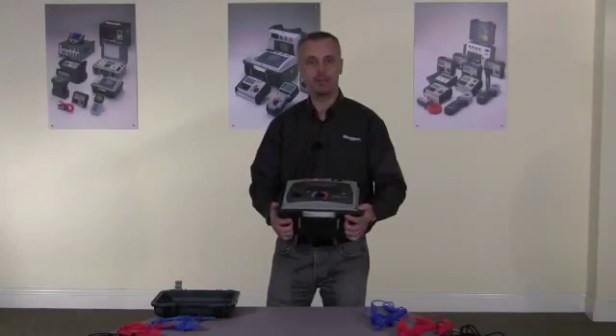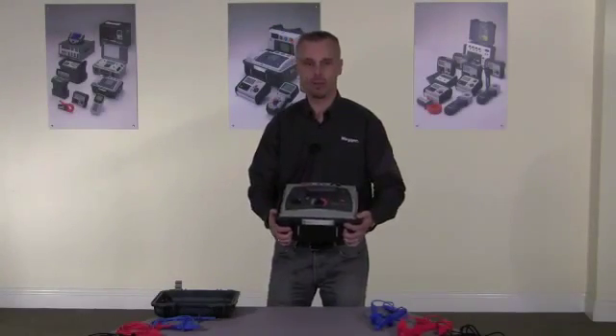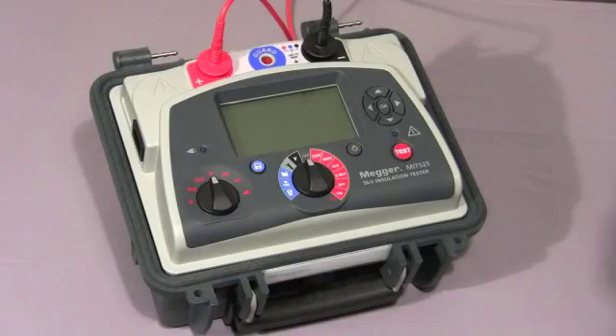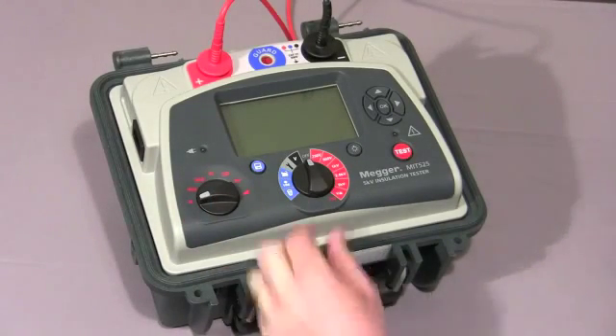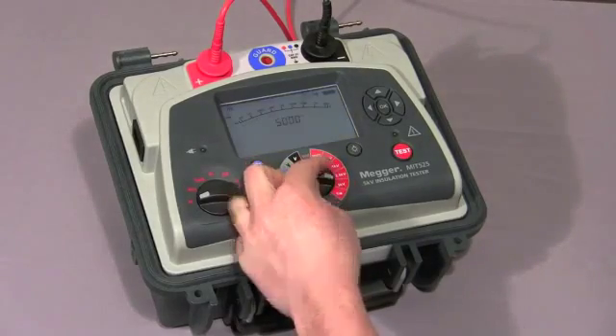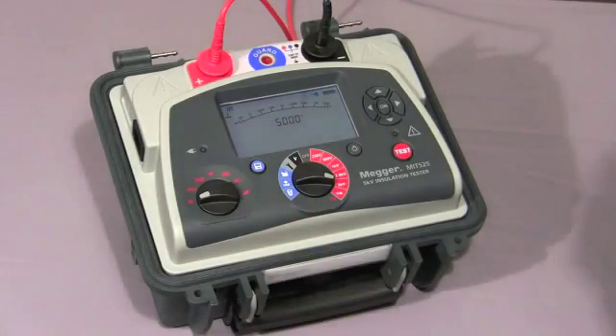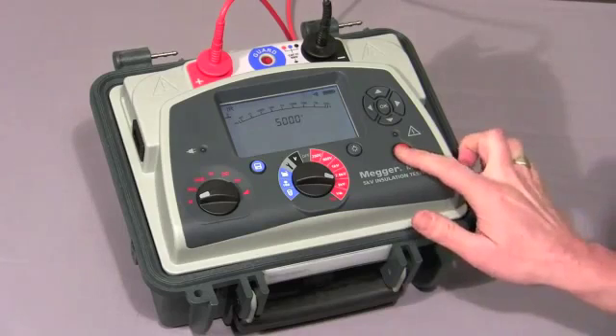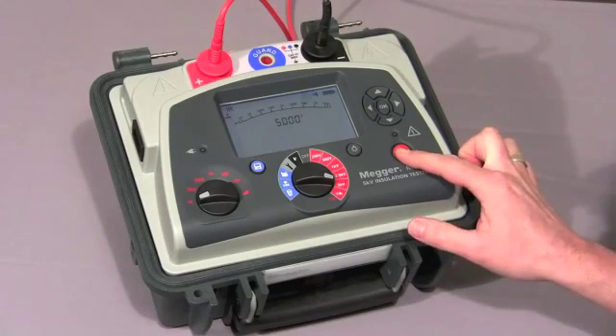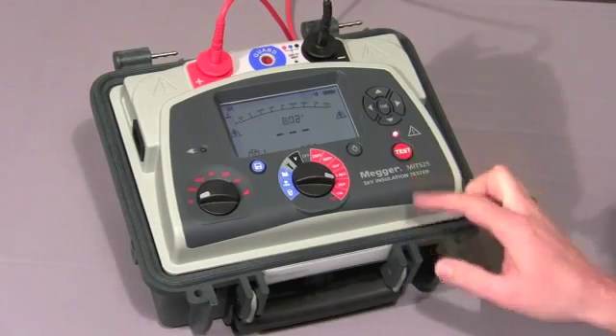I'd now like to take you through a full product demonstration. First of all, we're going to do a simple insulation resistance test. Move the mode switch to the IR position, then select the voltage I require, in this case 5000 volts, and then press and hold down the test button until the test starts.